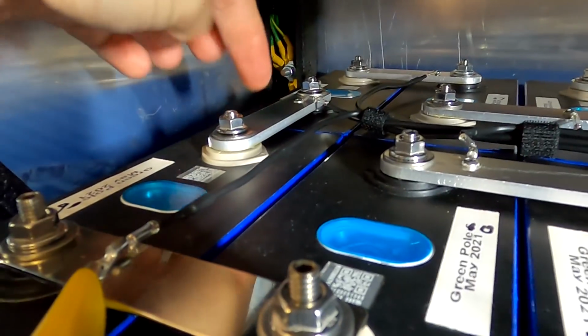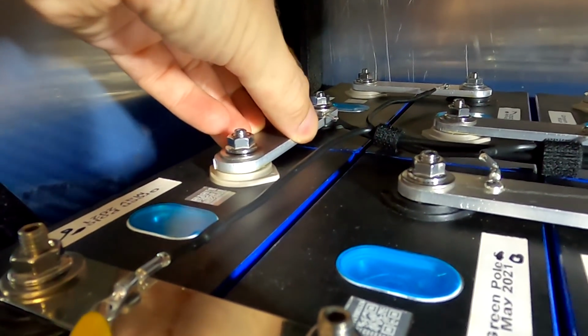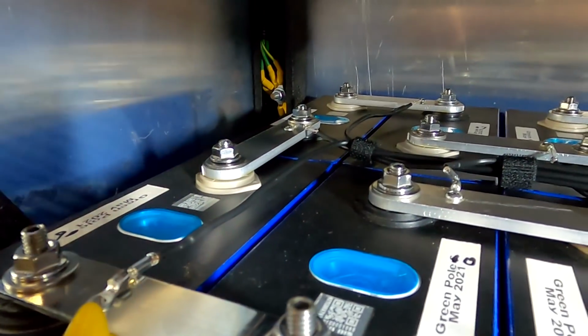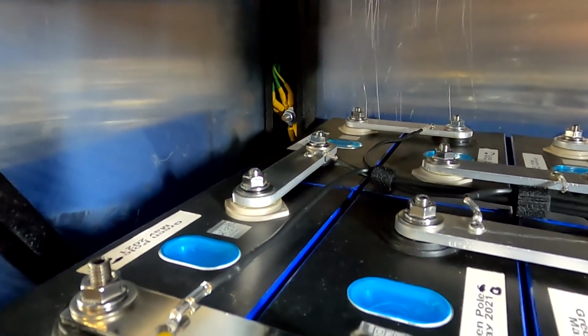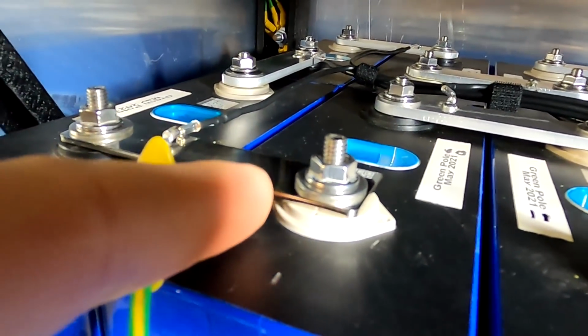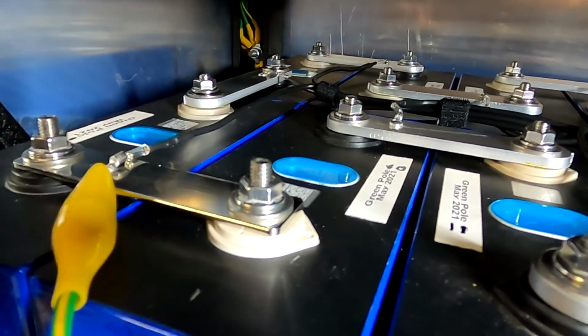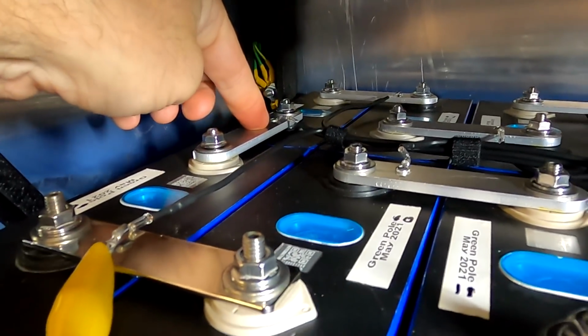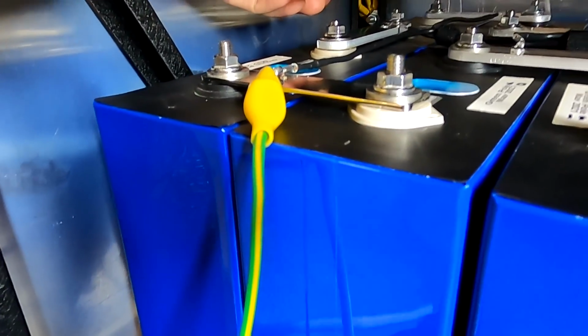So I've loosened the nuts now and moved the bus bar a little bit back and forward to clean the contacts, but this didn't make any difference at all. But I wonder why this one is not heating up anymore. I'll try to replace this one with one of Maddie's flexible bus bars and see if it makes a difference.